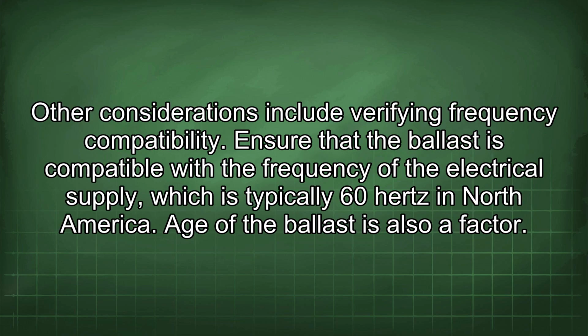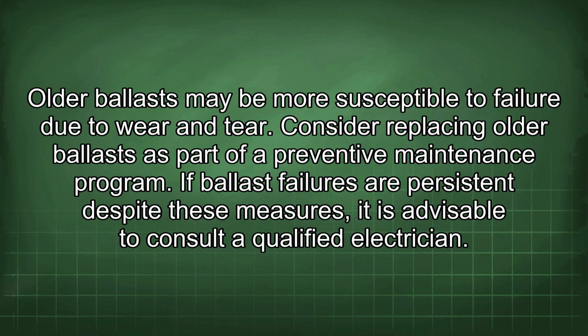Other considerations include verifying frequency compatibility. Ensure that the ballast is compatible with the frequency of the electrical supply, which is typically 60 Hz in North America. Age of the ballast is also a factor. Older ballasts may be more susceptible to failure due to wear and tear. Consider replacing older ballasts as part of a preventive maintenance program.